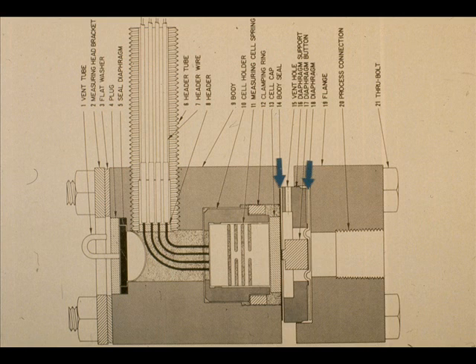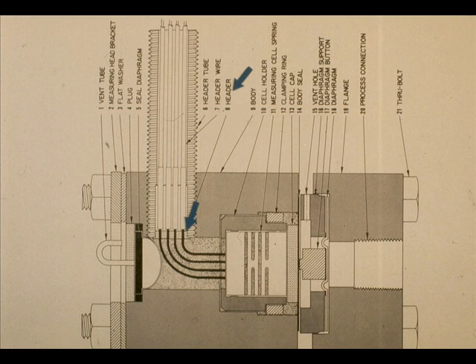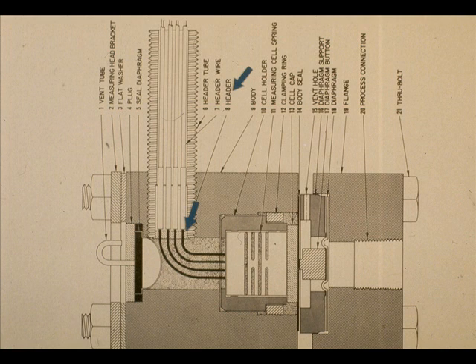The seal diaphragm 5 and the body seal 14 are provided to hermetically seal the measuring head body 9. If overpressure should rupture the measuring diaphragm 18, the body seal 14 should be checked for damage.